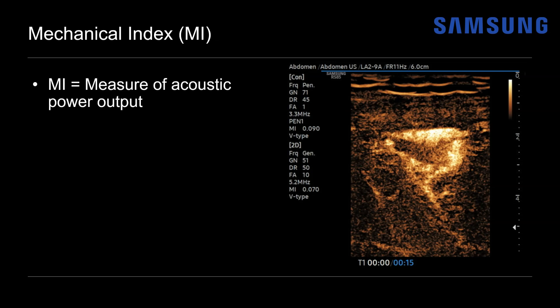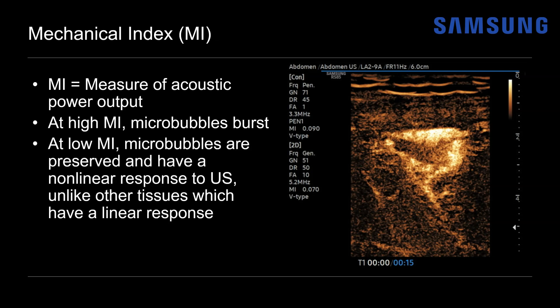The mechanical index is a measure of acoustic power output. At a high MI, because of this high acoustic power, the microbubbles are so delicate they'll actually burst. At a low MI, the microbubbles are preserved and will have a nonlinear response to the ultrasound beam — different from surrounding tissues, which have a more linear response. This allows us to create this vascular-only image.